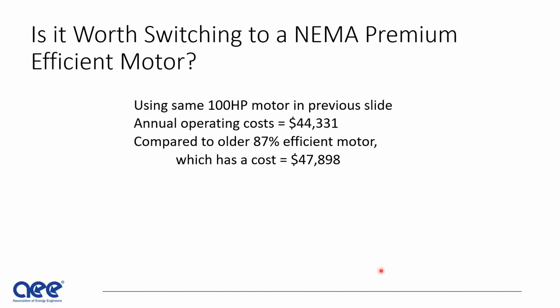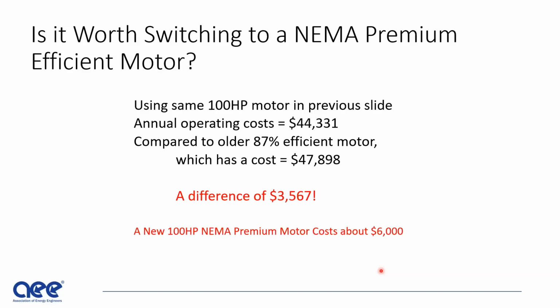Is it worth switching to a NEMA premium? Absolutely. Using the same 100 horsepower motor in the previous slide, the annual operating cost is $44,000 compared to an older 87% efficient motor, which has a cost of $47,000. It's a difference of $3,500, closer to $3,600. So you're looking at essentially less than a 2-year payback if the motor costs $6,000.